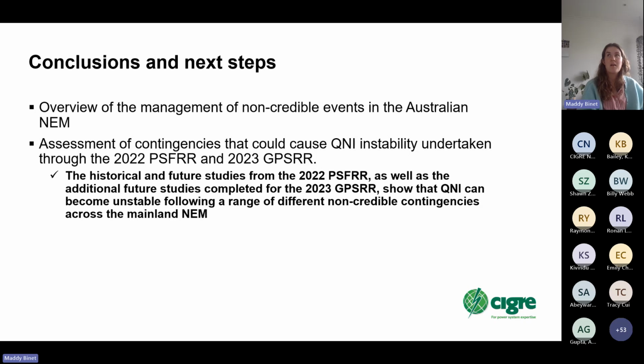I'd say as well, it's important to use EMT or PSCAD for anything looking at unbalanced faults or oscillation events, where you need a shorter time step that's not linearized. But the issue is you can't look very far into the future, because you need accurate system models that are representative of the actual plant. So usually we only do EMT studies looking up to 2 years ahead. That's all a consideration when we look at what risk we're studying, whether it's frequency or something else, and there's lots of assumptions in terms of what we're not able to capture and therefore what we are or aren't able to conclude from the study results.